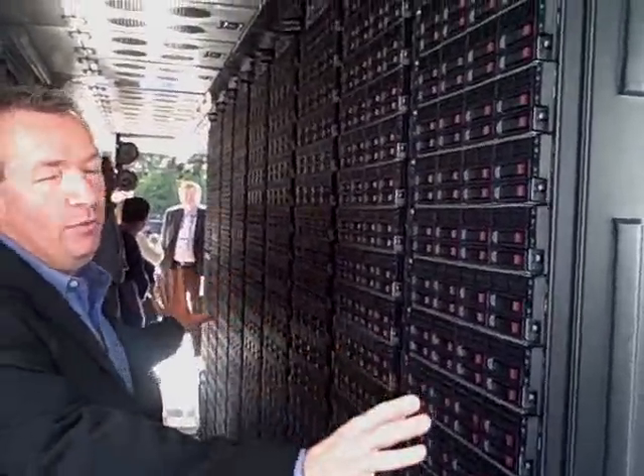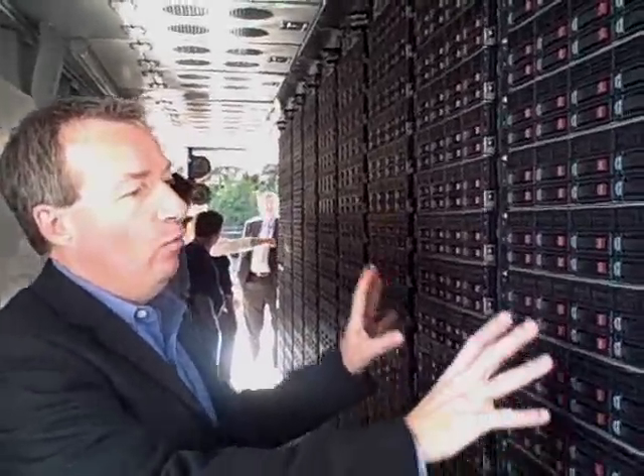The racks of IT here would extend all the way down the length of the pod. We've taken some racks out in this case because we wanted to have room for people to come in. Usually they would extend the entire length of the pod, and we've designed these racks to support any kind of equipment you'd put into a full-depth 19-inch rack in your data center — so it's not just HP equipment. You can put in Dell, IBM, Sun, etc.